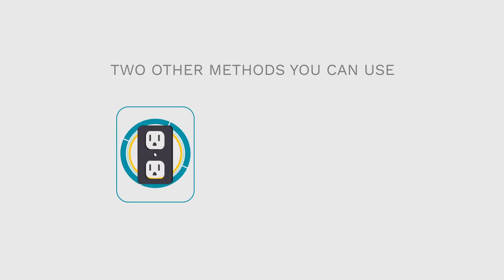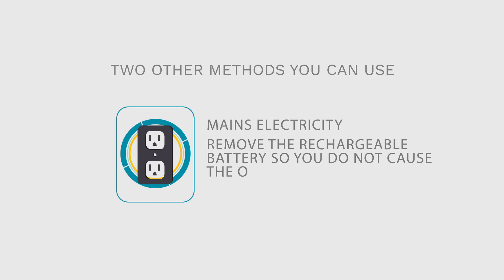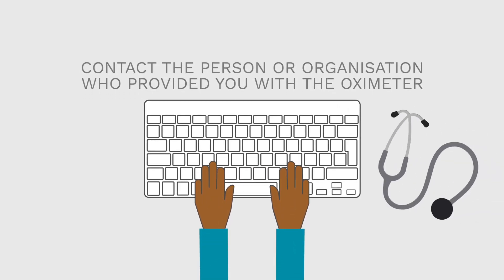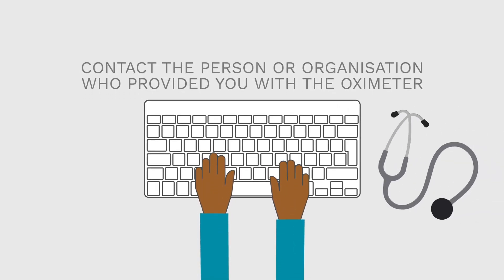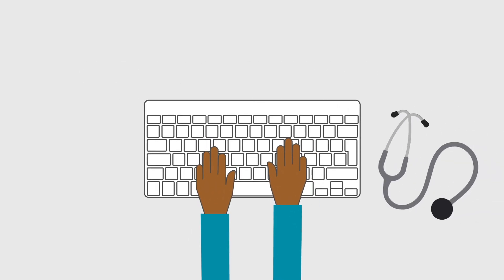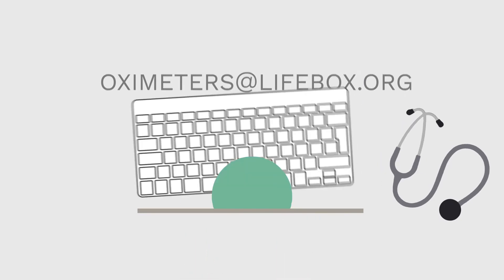You can also use the oximeter directly from the mains electricity. If you're going to use this method on a long-term basis, remove the rechargeable battery so that you do not cause the oximeter to overheat. If your rechargeable battery stops working, contact the person or organisation who provided you with the oximeter, or contact Lifebox directly.